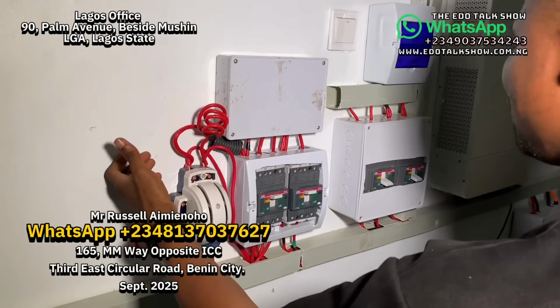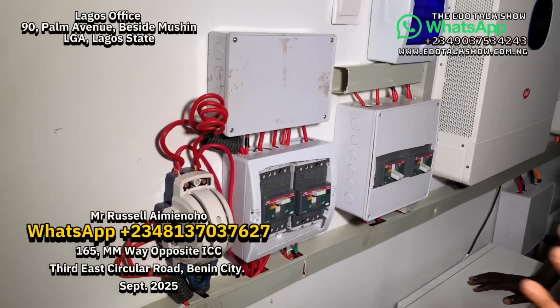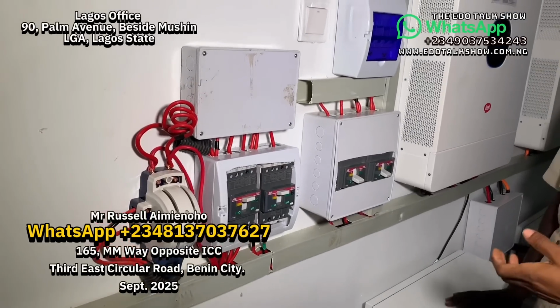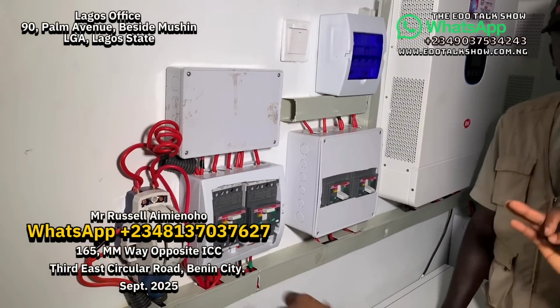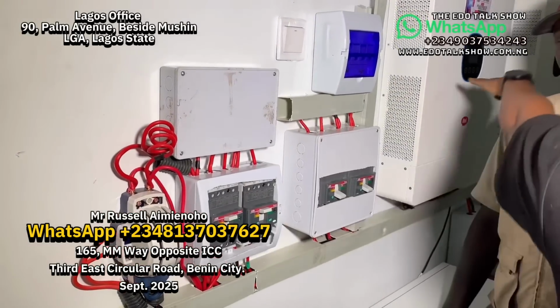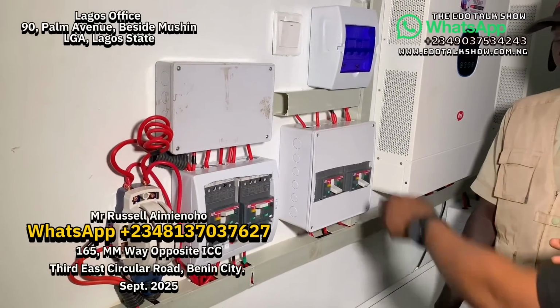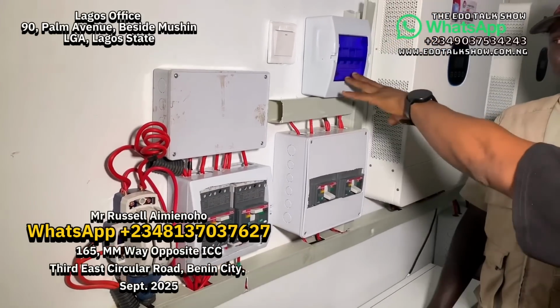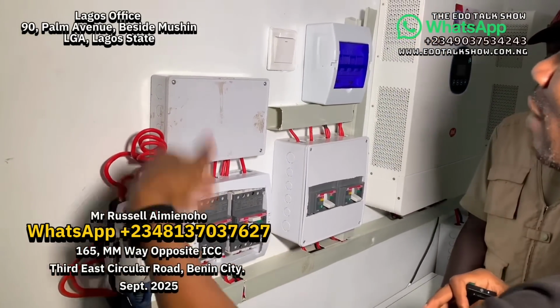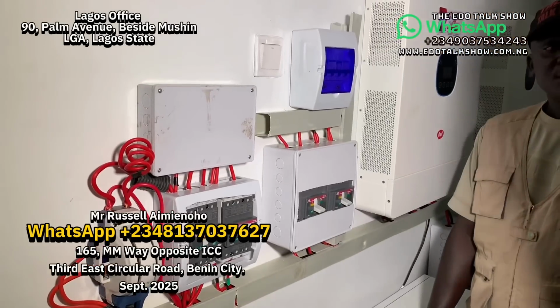We also put a bypass switch here, that bypass switch we get from NEPA. In case God forbid this inverter has an issue and oga wants to use a generator, you can just switch off this inverter, off the breaker for the battery, off the breaker for the solar panel, carry this changeover and pull up for bypass. Then the generator, wherever the owner has it, like central gen, can go enter the house before we come fix whatever challenges we have.